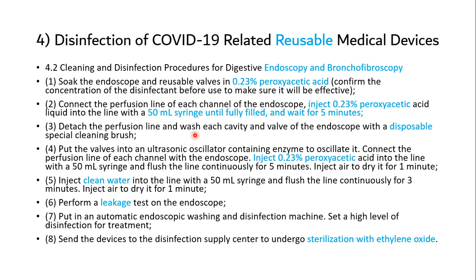Detach the perfusion line and wash each cavity and valve of the endoscope with a disposable special cleaning brush. Put the valve into an ultrasonic oscillator containing enzyme to oscillate it. Connect the perfusion line of each channel with the endoscope. Inject 0.23% peroxyacetic acid into the line with a 50 ml syringe and flush the line continuously for 5 minutes. Inject air to dry it for 1 minute. Inject clean water into the line with a 50 ml syringe and flush the line continuously for 3 minutes. Inject air to dry it for 1 minute.